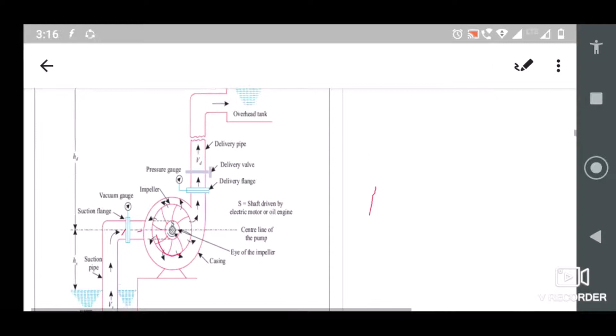Here you have different kinds of heads. First you have the suction head, which is the vertical height from the center axis of your impeller down to the ground level of the water. And we also have the delivery head, which is the height above the center line of the axis of your impeller to which the water is delivered.